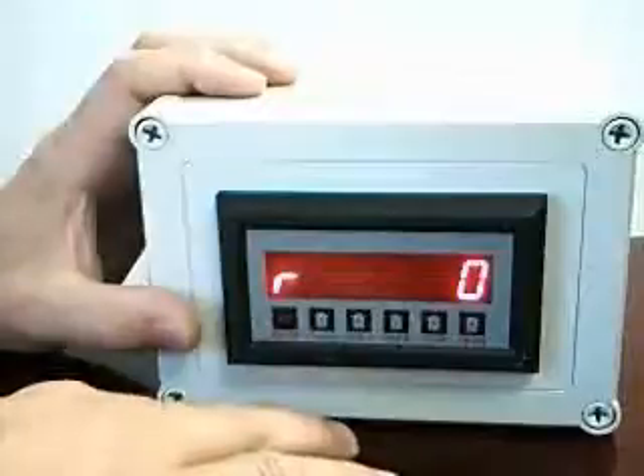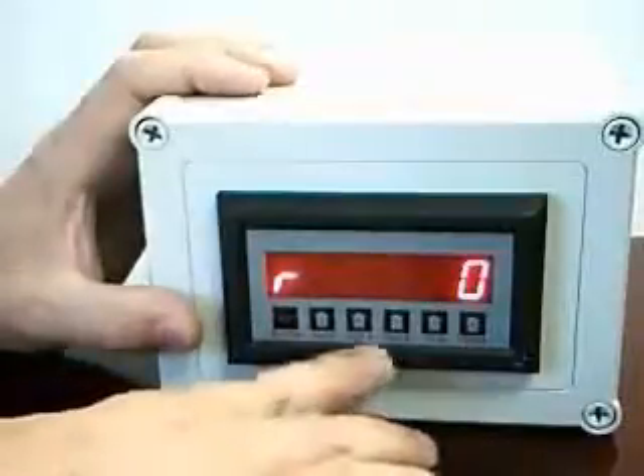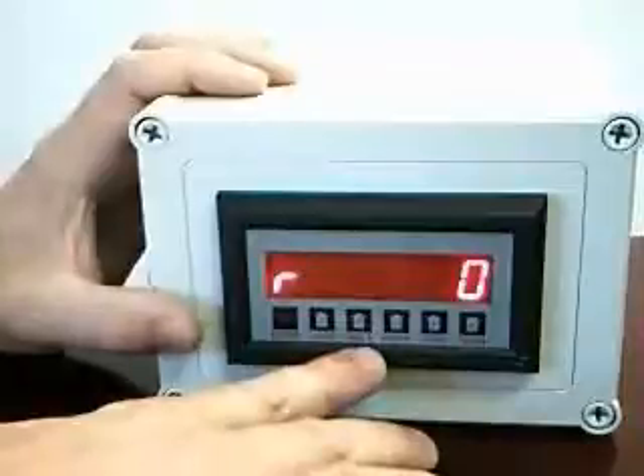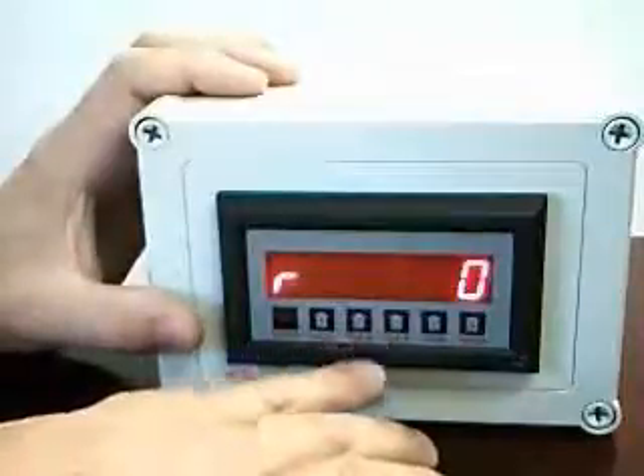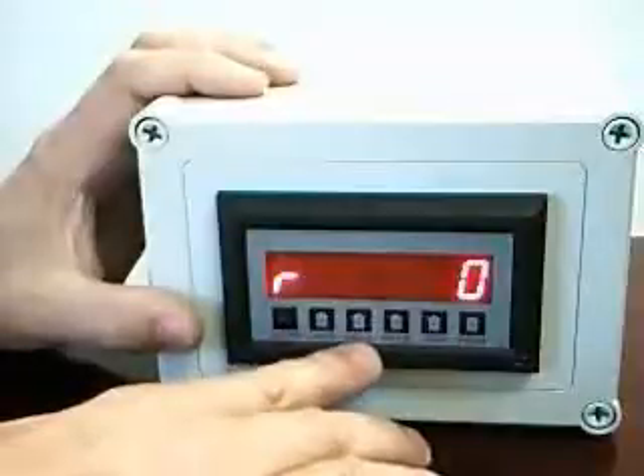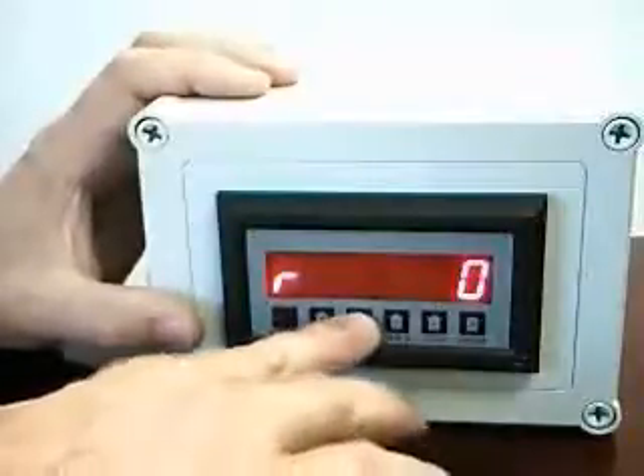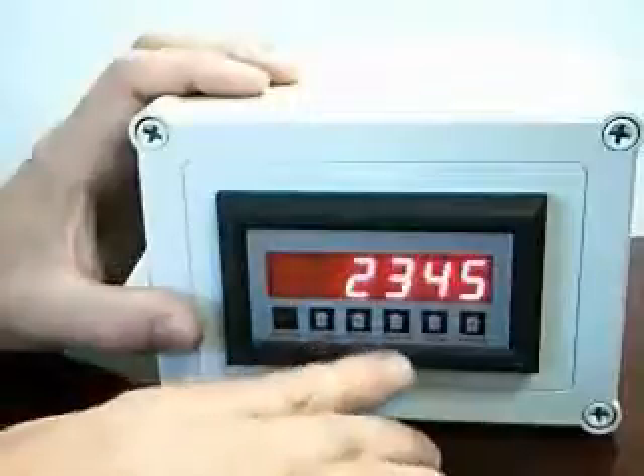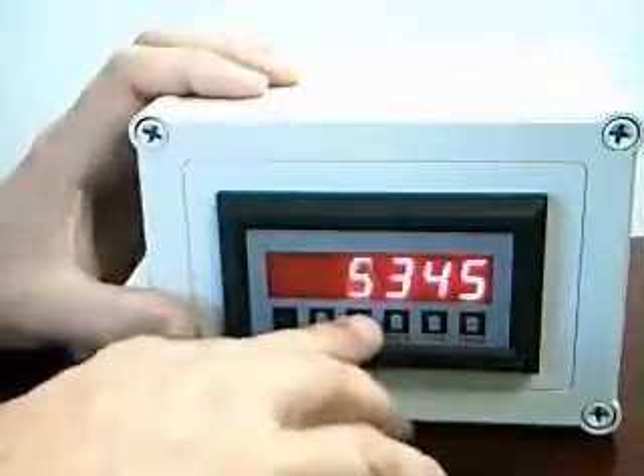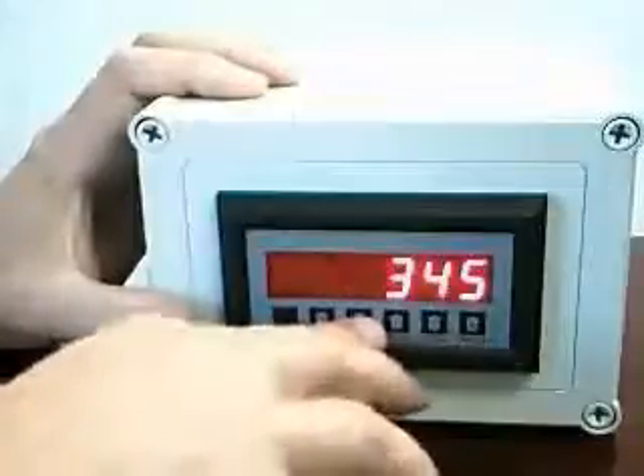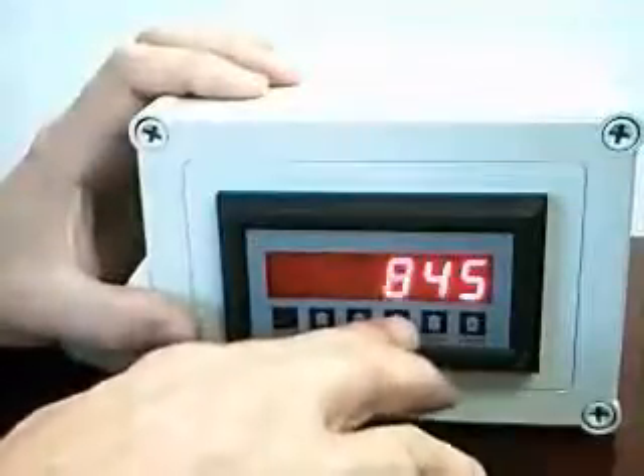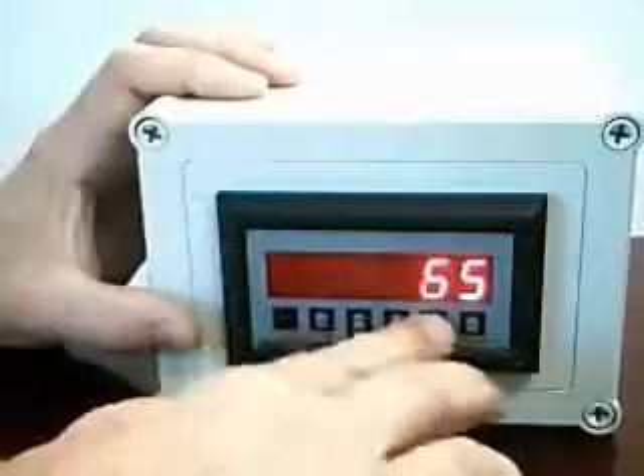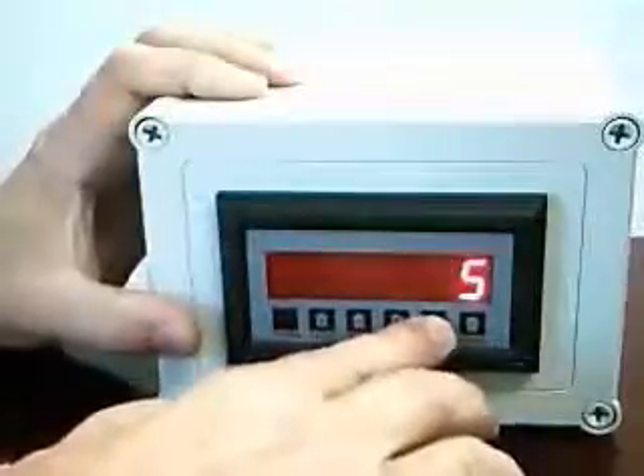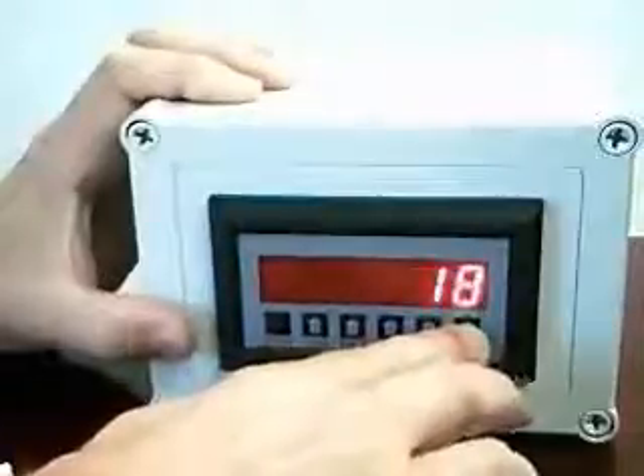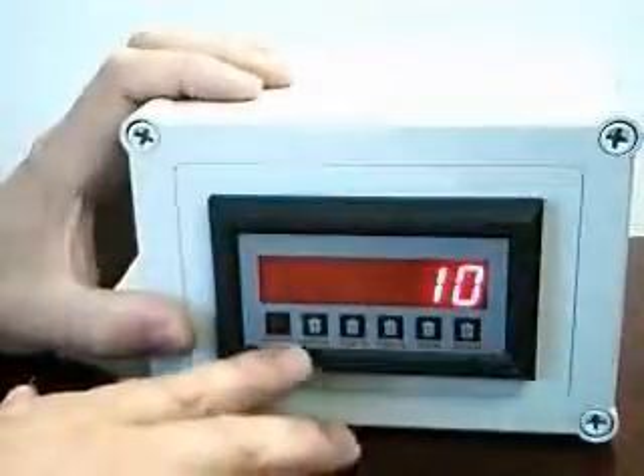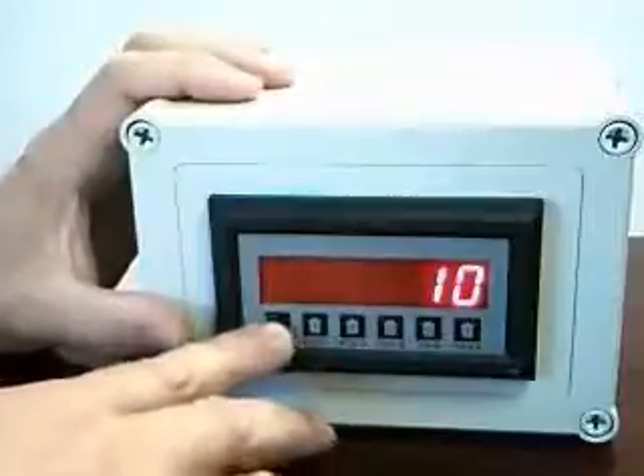Let's assign these 2 alarms, the first to 10 gallons a minute and the other to 90 gallons a minute. To change the alarm on rate A, I will press pre-A and then go through and change the digits one by one until I observe 10 on the display. Once I'm satisfied with the settings, I can press enter.